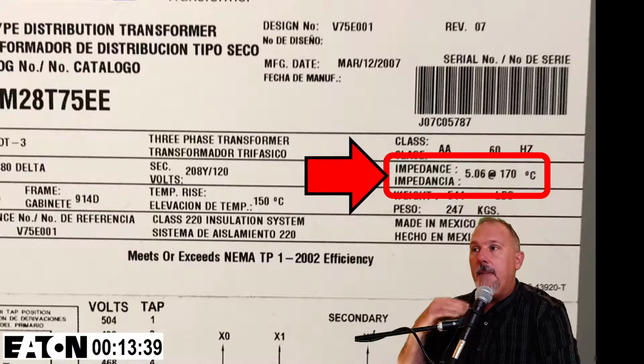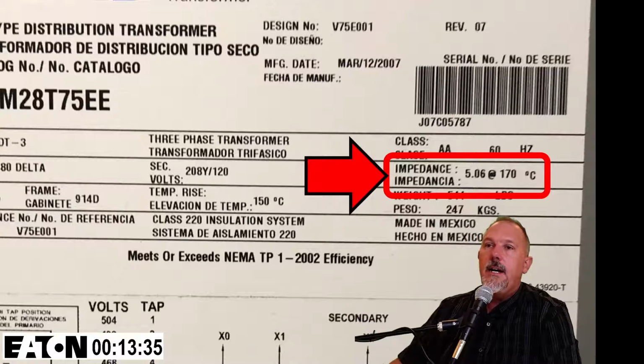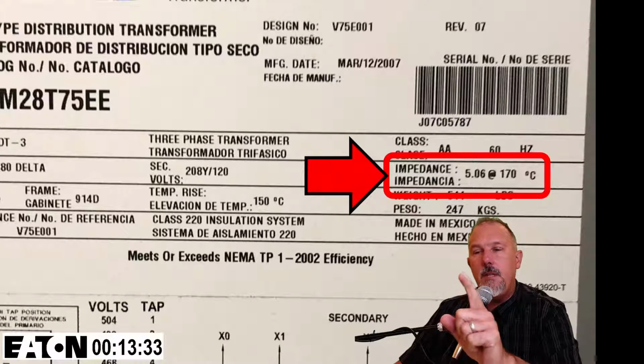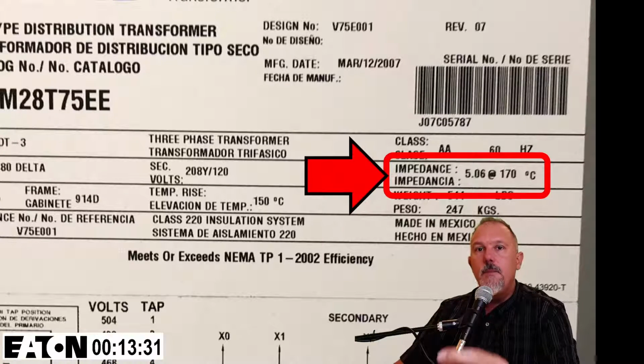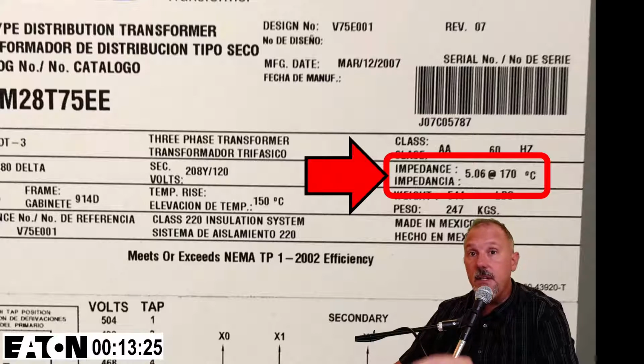All right, so the impedance of this transformer is 5.06%. And that transformer impedance is going to be important for me to determine the available fault current on the secondary, the maximum infinite bus calculation of available fault current on the secondary of this transformer, so that I pick the right interrupting ratings for those secondary overcurrent devices.